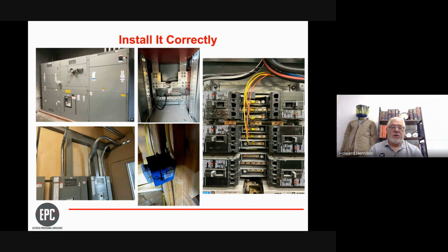Just threw a couple pictures up here. The first two are pretty good installations. Down here at the bottom left, they might have done a fairly decent job installing the pipe, but they forgot the supports for it. And they created a hazard by cutting holes in the electrical room, which has to have a 2-hour fire rating, and not refilling those holes.